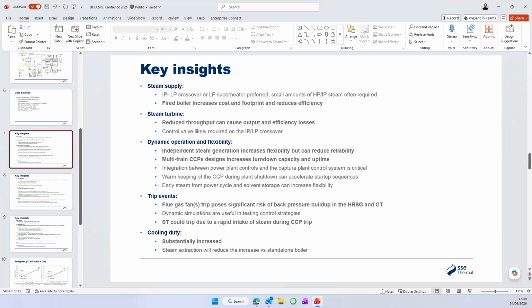Likewise, your ST could be at risk in the case of a CCP trip, because basically your steam supply to your CCP might back off, and then you get a massive increase in flow through your steam turbine, which could trip it. I already mentioned, but cooling duty substantially increased as a result of including a CCP, but that impact is reduced if you use steam extraction from your power system rather than having a standalone fired boiler, because you move the duty from your condenser elsewhere to the CCP effectively. So that can be mitigated somewhat that way.